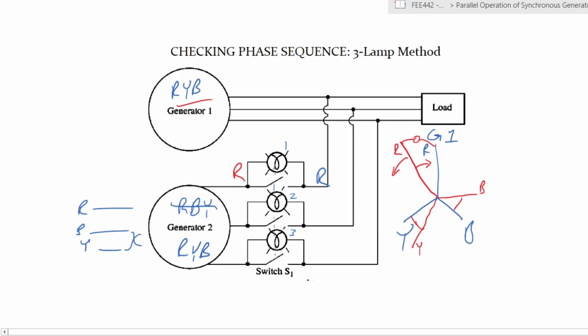So what the lamps are actually showing is the phase difference between the two. As long as there's a phase difference between the two, there will be some voltage circulating between them. So the aim of checking the phase sequence is to ensure that you can see the brightness or dimming going in the same sequence, right? So let's look at it a bit more in terms of proper synchronization.